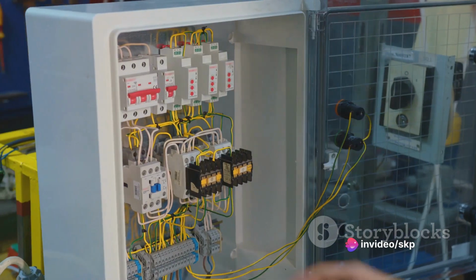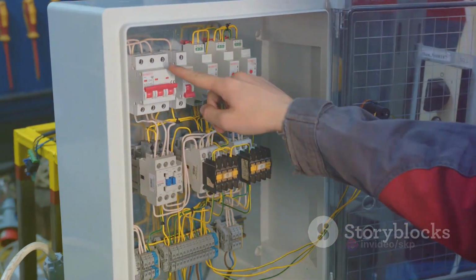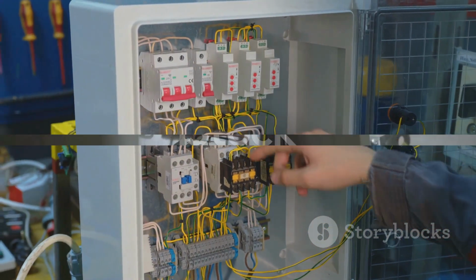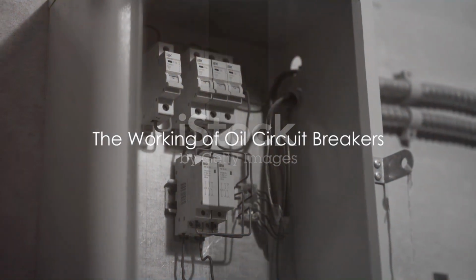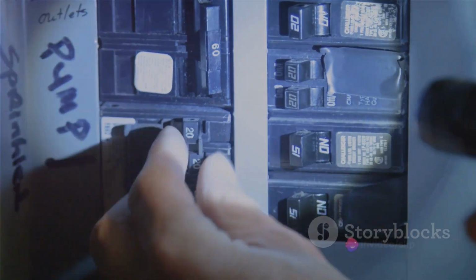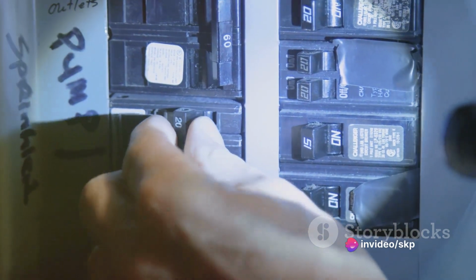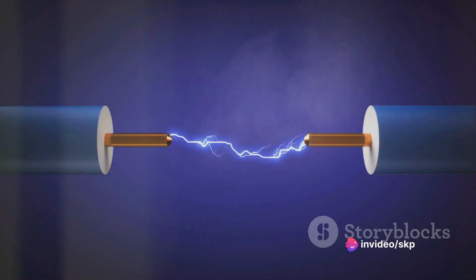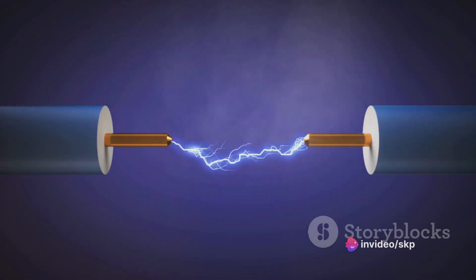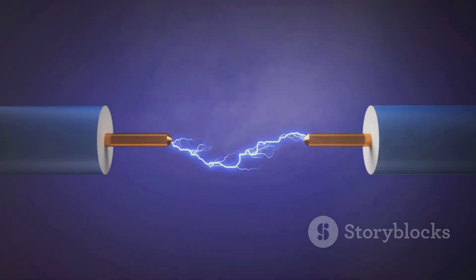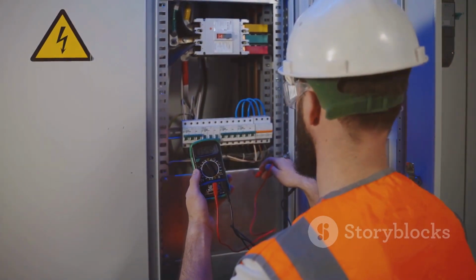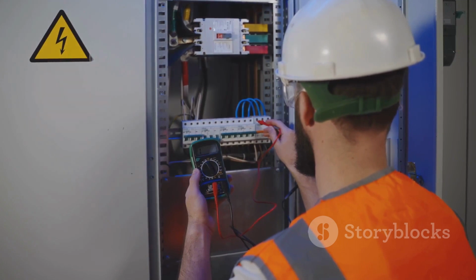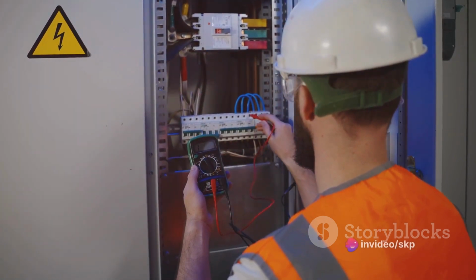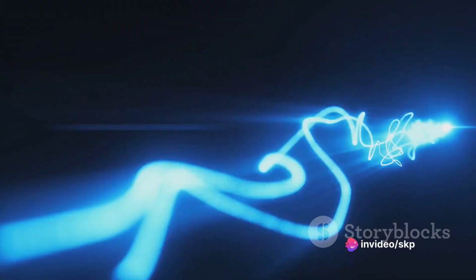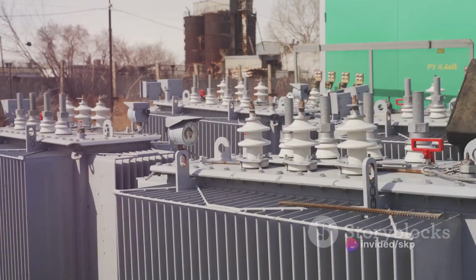Now let's delve into the details of one particular type of circuit breaker, the oil circuit breaker. So, how does an oil circuit breaker work? I'm glad you asked. Picture this, an electrical fault occurs, and the current surges. This surge of electricity races through the oil circuit breaker, reaching the contacts. The contacts, sensing the fault, begin to separate. As the contacts move apart, an electrical arc forms between them. This arc, a spectacular display of electricity jumping across the gap, generates intense heat.